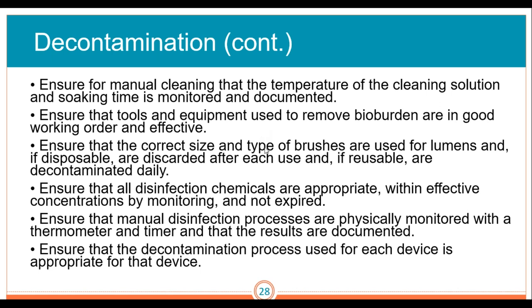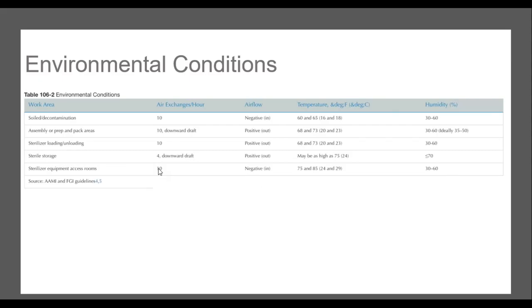We have about 15 minutes left, so let's get to some questions. These are our environmental conditions. Your soiled and decontamination area: 10 air exchanges per hour, negative pressure. I always remembered that decontamination is negative and has the lowest temperature: 60 to 65°F, and humidity 30 to 60%. When in doubt on humidity, go with 30 to 60.